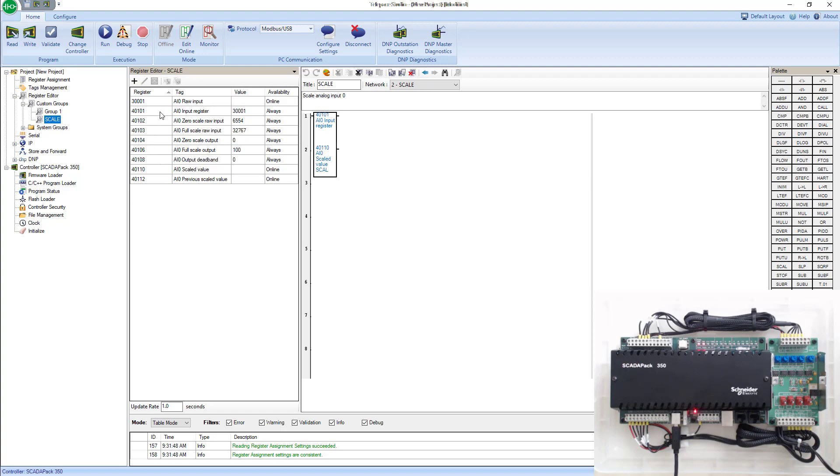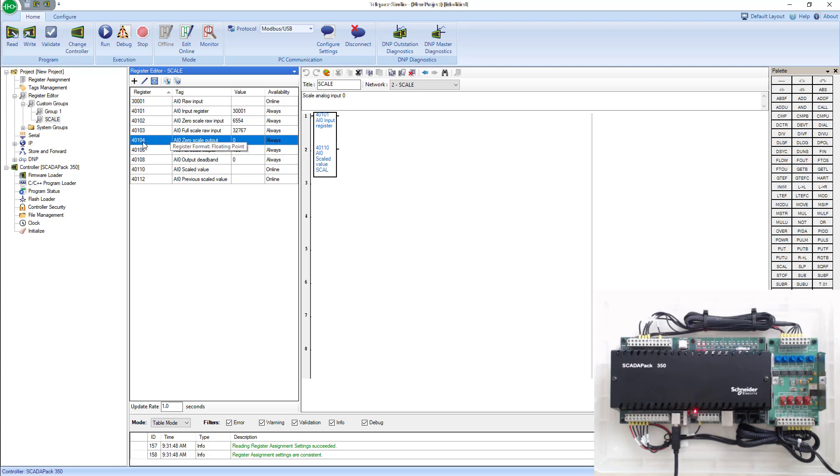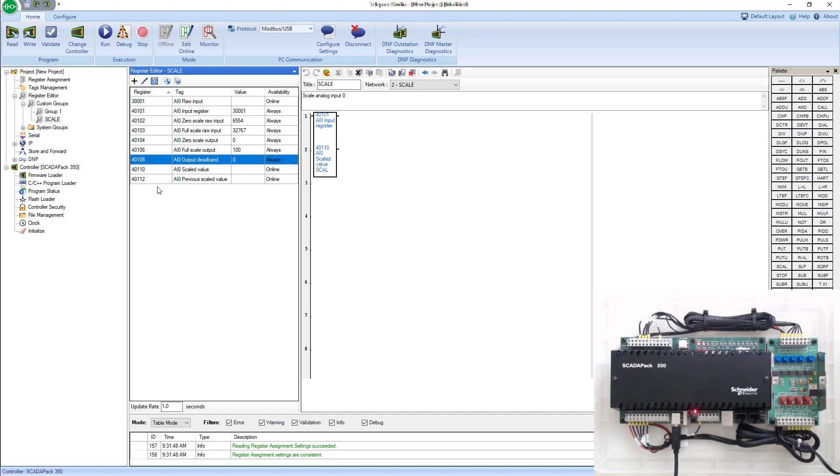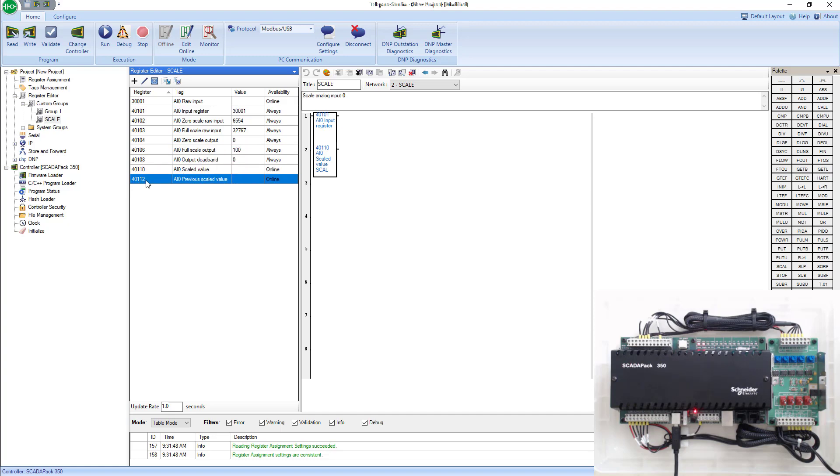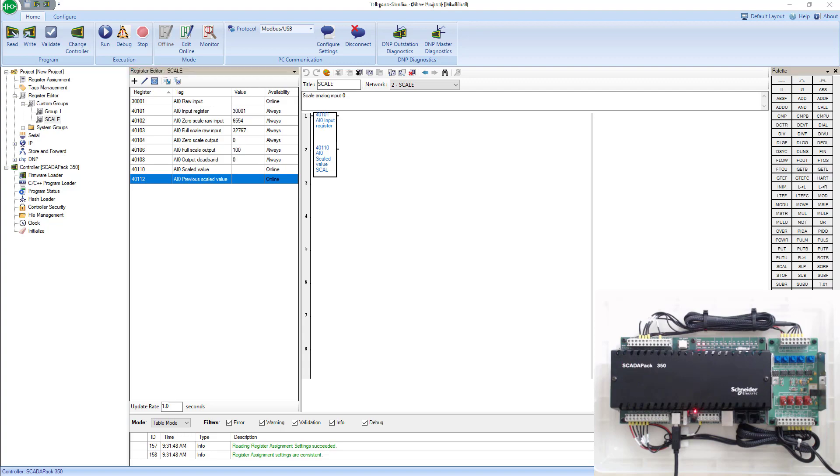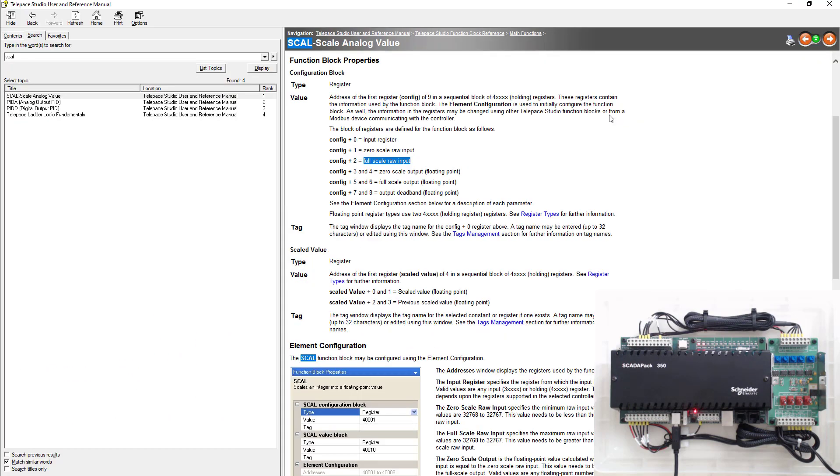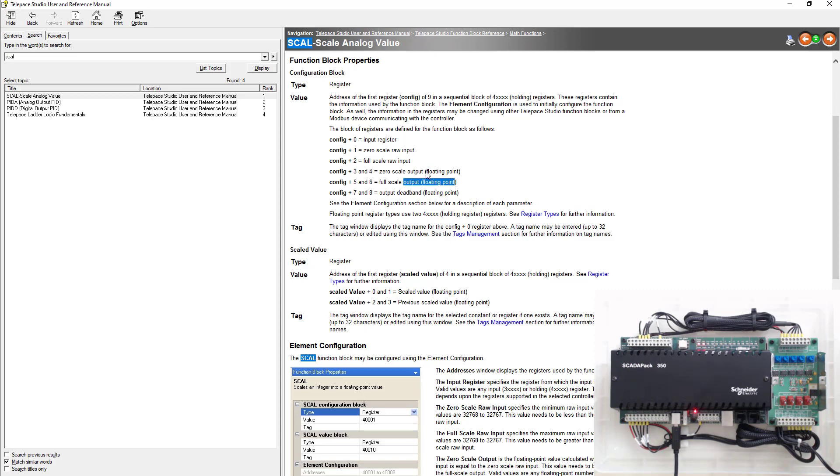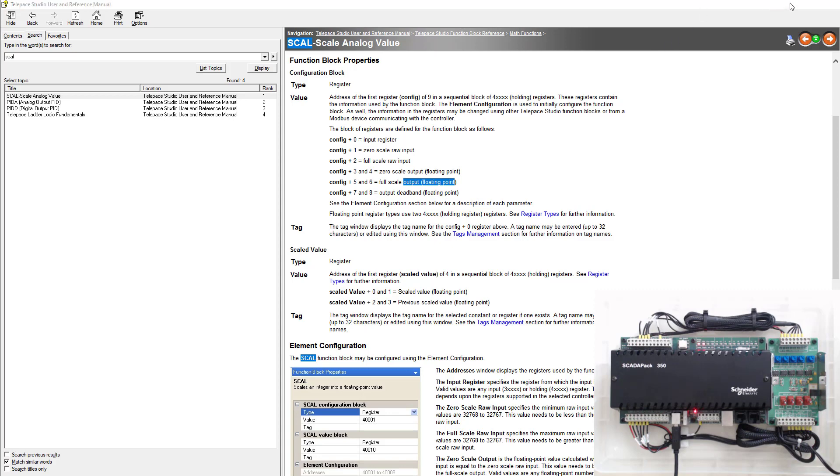One thing you've got to be aware of is some of these are floating points. This value here is a floating point, so you know that 40,104 and 40,105 are used in this tag. In the next tag, you've got to go two more. So this is 40,106, and then it's 108. Same with the scaled output. It starts at 40,110. It's a floating point, so this one started at 40,112. You'll notice that from the help manual as well. It uses two registers because it's a floating point. Just be aware of that.